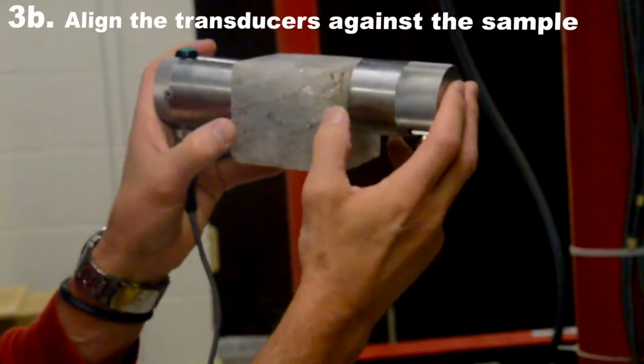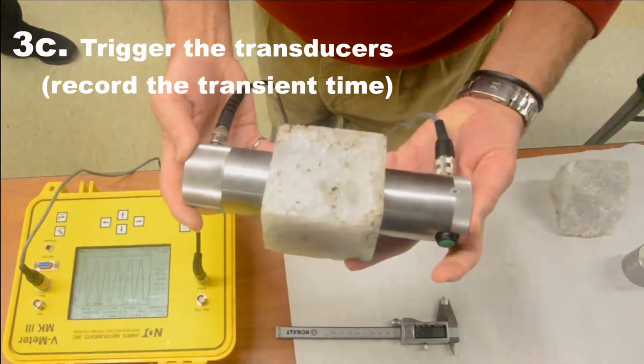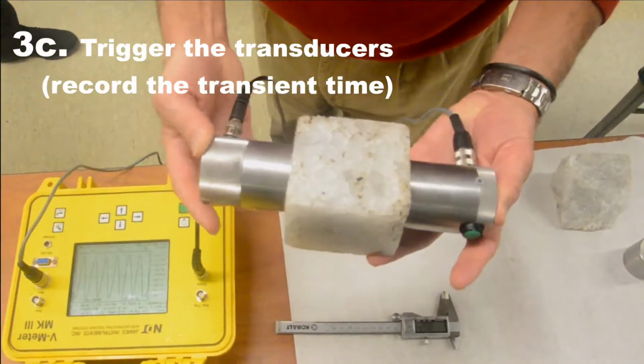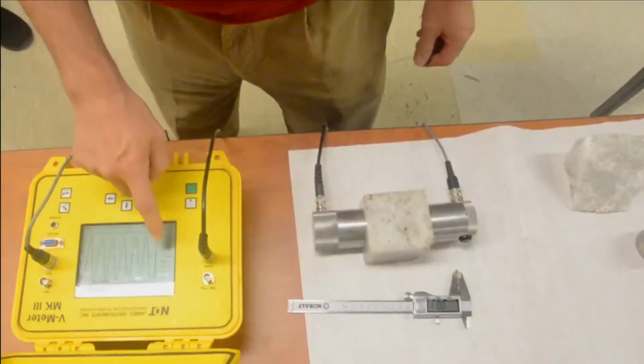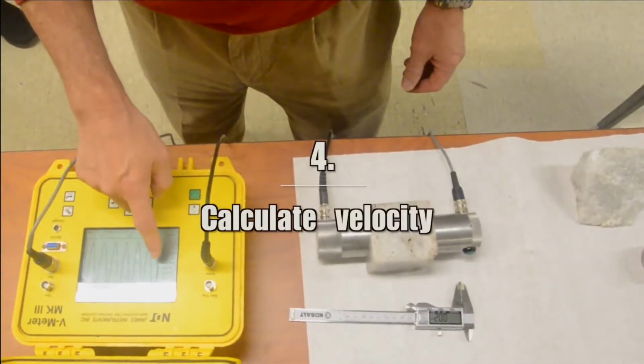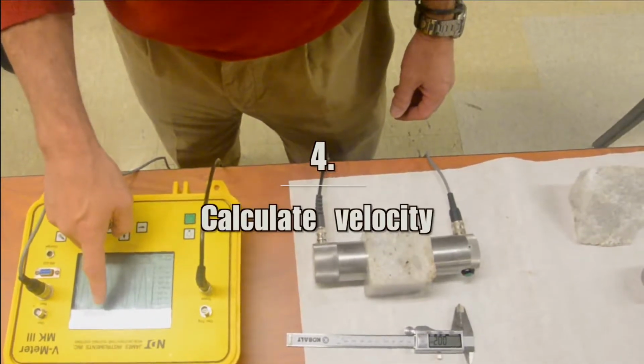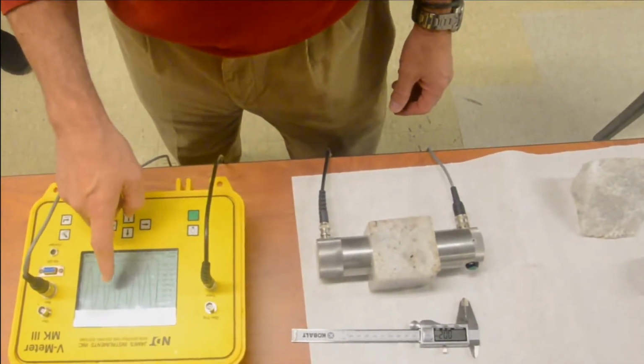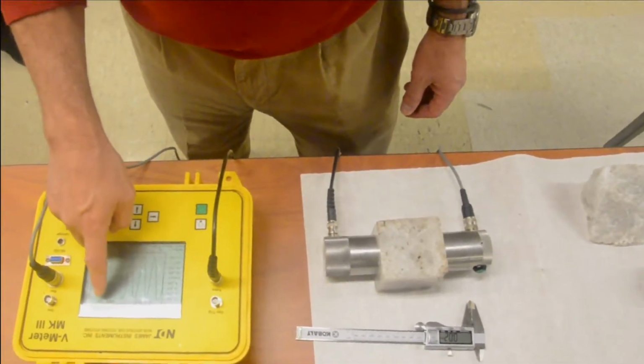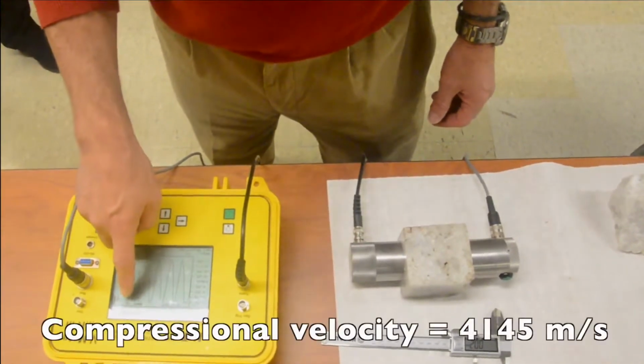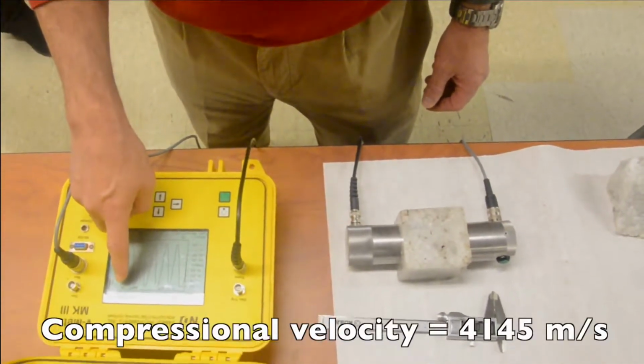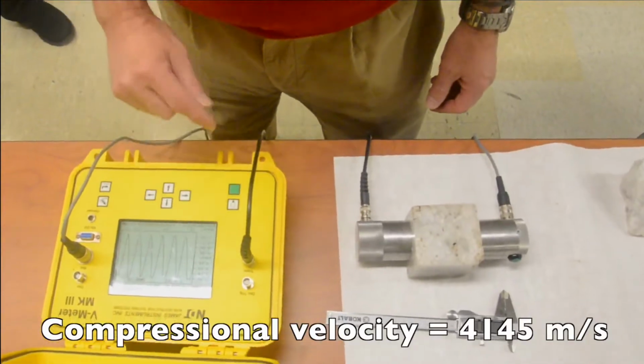Then we're going to put them on the sample and find the time of flight from the source through the material to the receiver. To make a pulse, the pulse goes through the sample, it's received, and sure enough, the instrument has picked a transit time, and having input the distance, that picked time, we calculate a velocity, and the velocity here now is 4,145 meters per second.